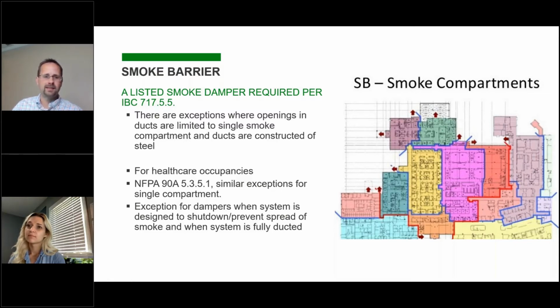So the places where we see that most often is if you have an air handler serving a suite or some rooms on a different side of the smoke barrier than the air handler is, and it just runs from, say, the mechanical room straight through the smoke barrier to serve an area. You can omit that smoke damper in that place. It's a little bit different than fire, because with fire, even if you run through a fire rated wall, a fire barrier, and you had no openings, you still have to have the damper. There's no exception in that, because fire can collapse the duct and there needs to be protection.